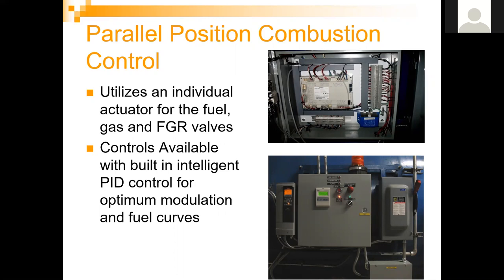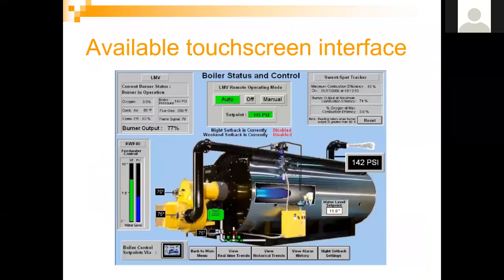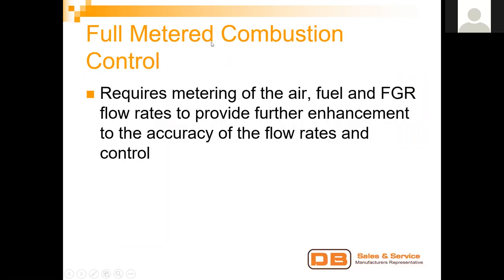Touch screens are becoming very common for monitoring oxygen and combustion efficiencies directly on the unit. Fully metered combustion control systems require actual flow meters on the air, fuel, and FGR streams — providing a mod motor on each while also monitoring and measuring flow rates of makeup air, fuel, and FGR to further enhance accuracy and control.